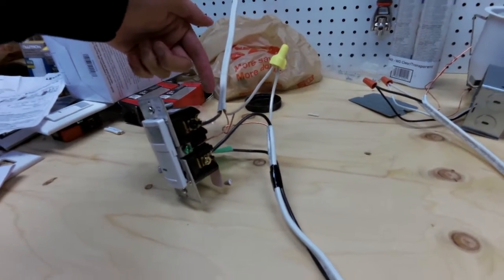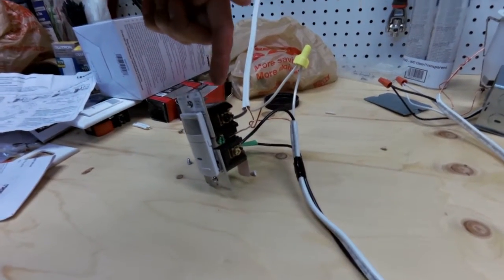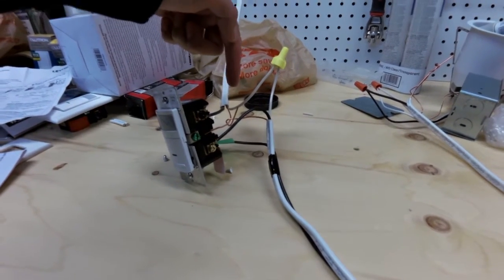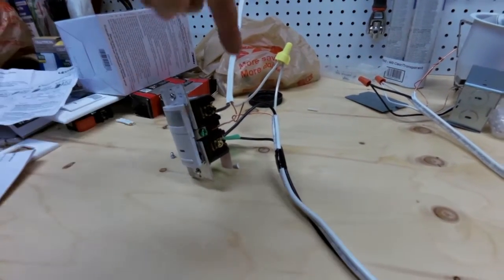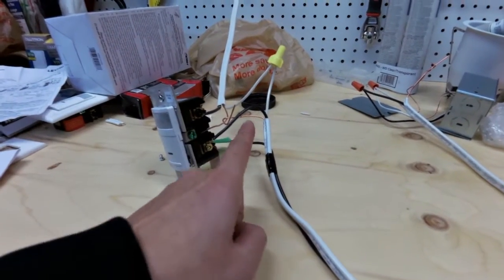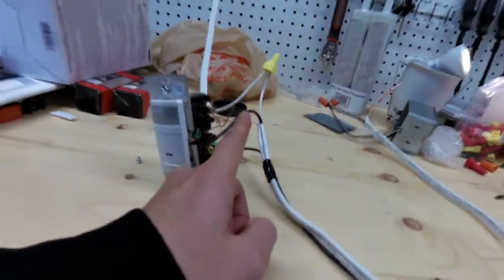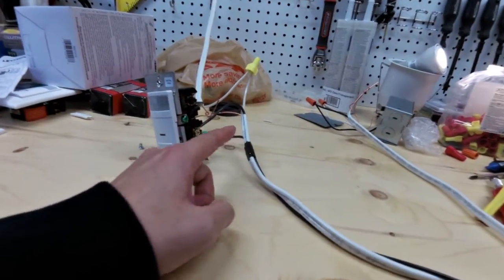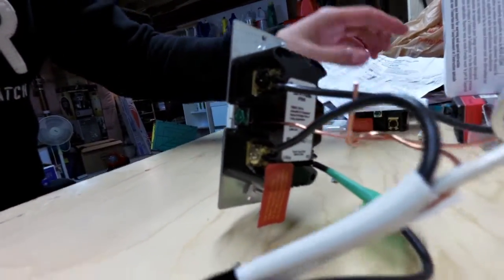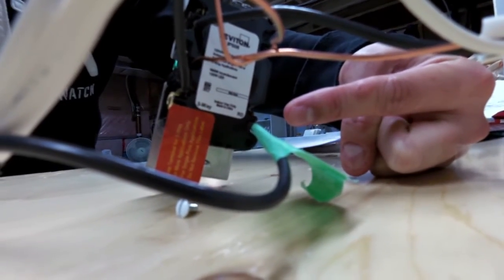You've got the hot wire, black wire coming down into the black common terminal. Bare copper wire for ground wire goes to the green terminal. Then the black wire from your 12-3 is going to go into the back here, which says the three-way. And then the red wire, which I have to short out on the other side, is going to be connected to the red terminal. So that's pretty much it.